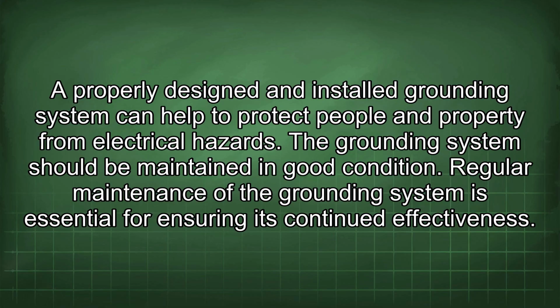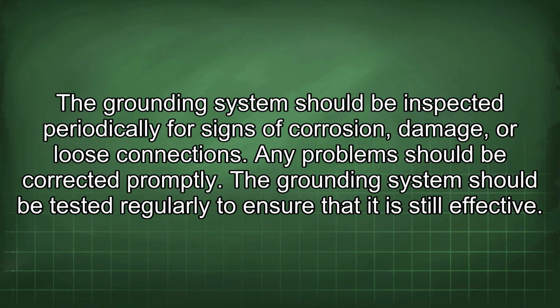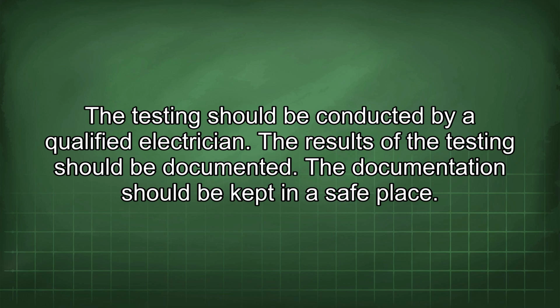The grounding system should be maintained in good condition. Regular maintenance of the grounding system is essential for ensuring its continued effectiveness. The grounding system should be inspected periodically for signs of corrosion, damage, or loose connections. Any problems should be corrected promptly. The grounding system should be tested regularly to ensure that it is still effective. The testing should be conducted by a qualified electrician. The results of the testing should be documented. The documentation should be kept in a safe place.